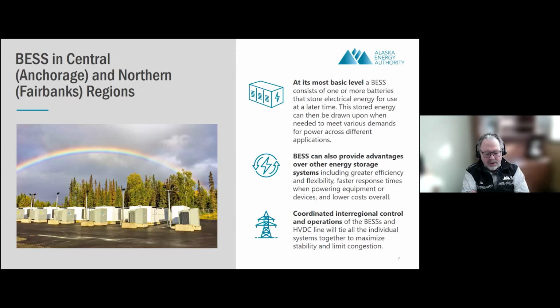They can absorb surges, help with some of the power oscillations, and do a lot of things. Fairbanks had installed a BESS over 20 years ago, and at the time it was awarded the most powerful battery system in the world, providing 46 megawatts for 5 minutes. This Homer BESS has the capacity of 94 megawatts for 1 hour, or 47 megawatts for 2 hours. So in 20 years, we've gone from 5 minutes to 2 hours worth of duration.